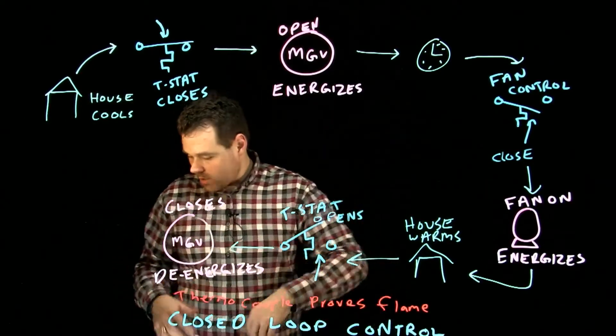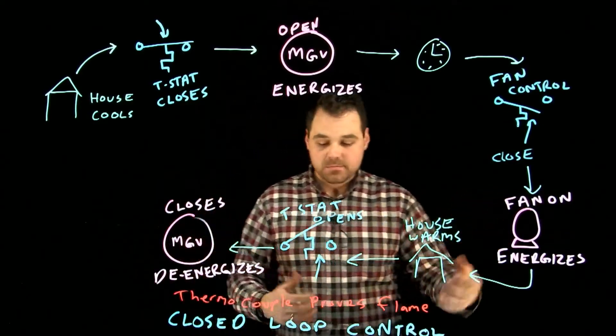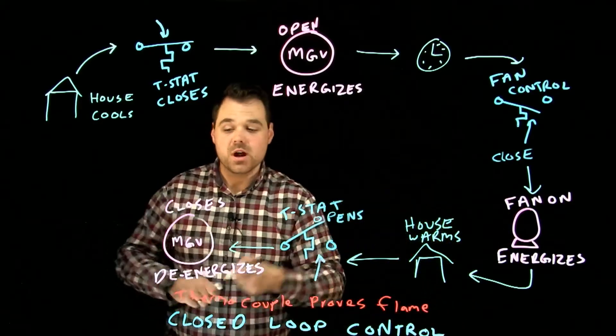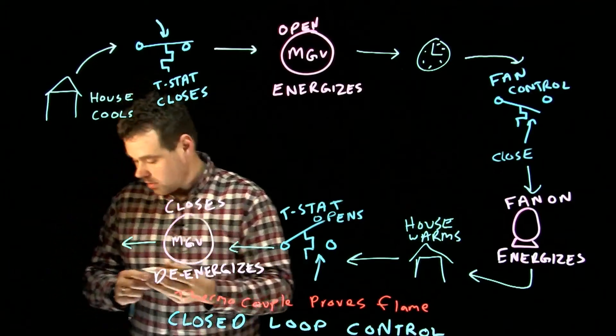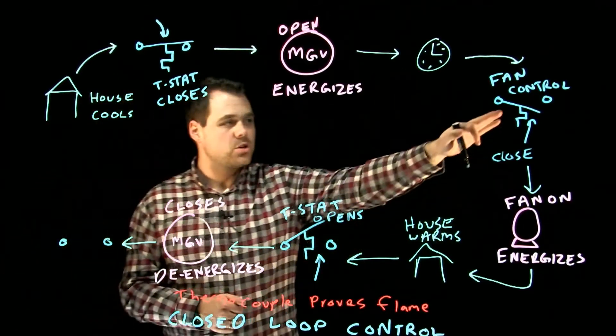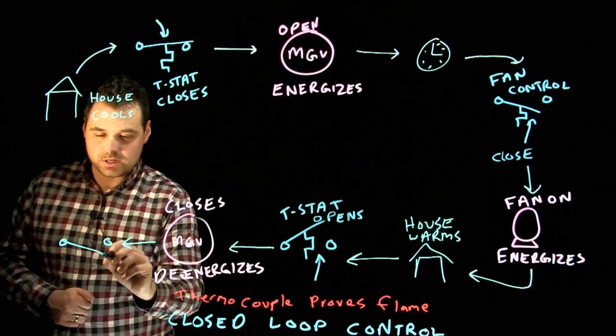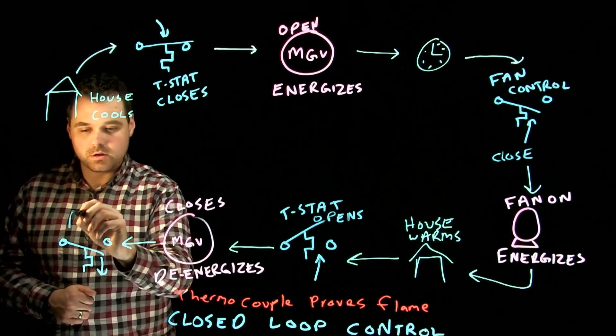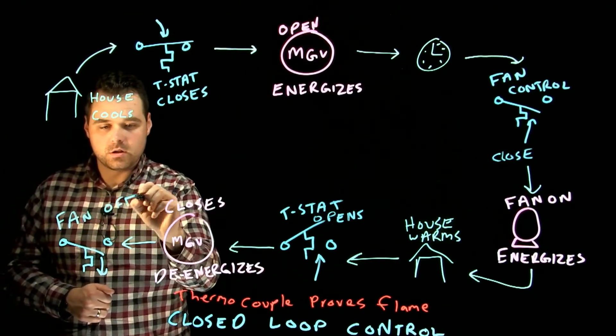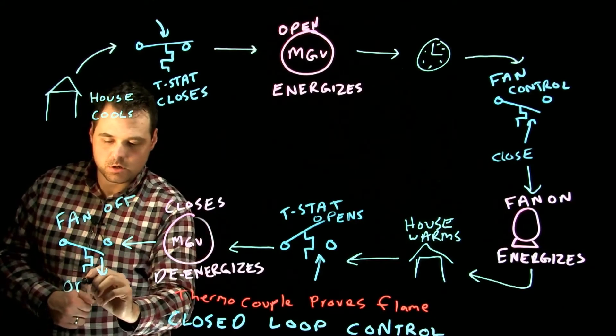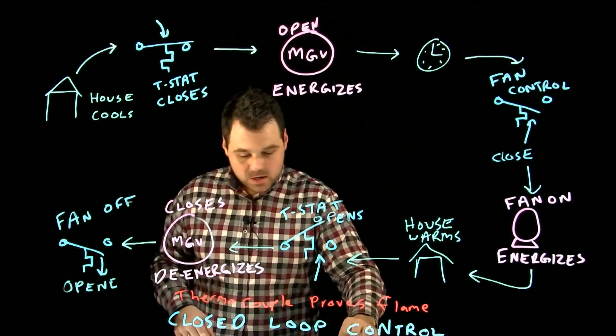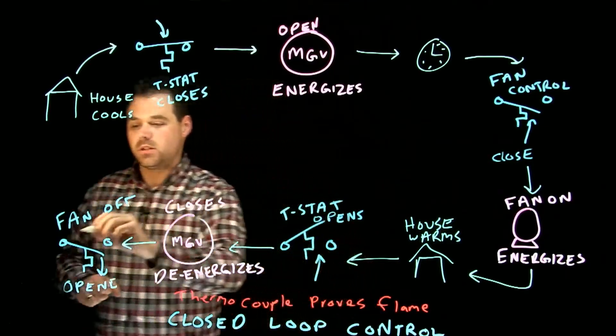Now that our main gas valve is closed, eventually our plenum begins to cool down. Once the plenum cools down enough, our fan control switch, that normally open switch that closed, is actually going to turn the fan off because the switch opened.